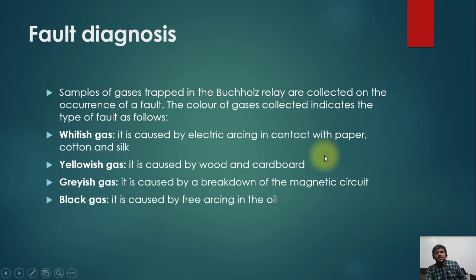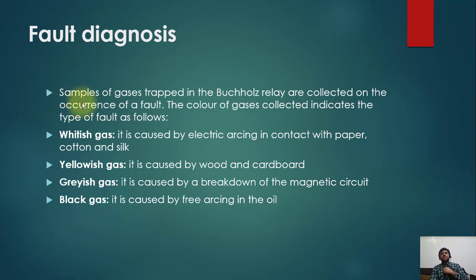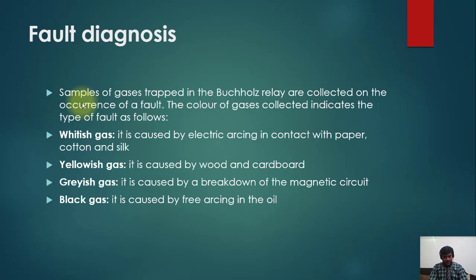The gas trapped inside the Buchholz relay can be used to diagnose the fault. A sample of gas trapped in the relay is collected upon occurrence of a fault. The color of the gas collected indicates the type of fault. When the Buchholz operates, special equipment can be used to collect the gas and send it to a lab, or it can be tested on-site.